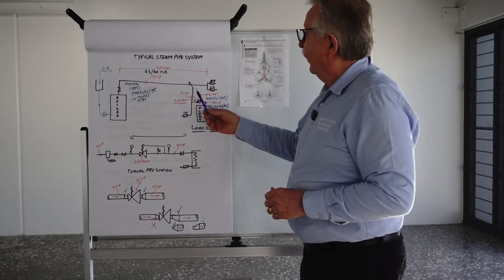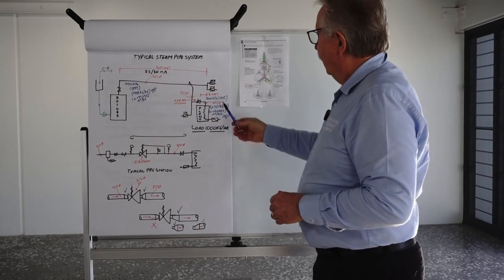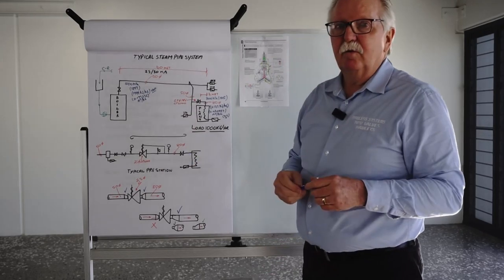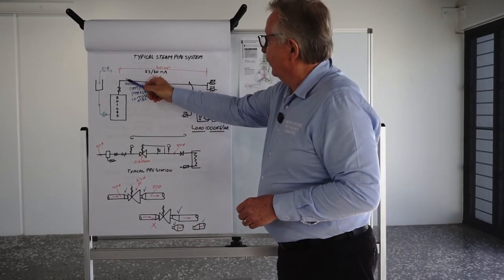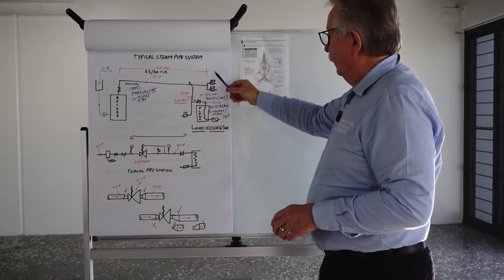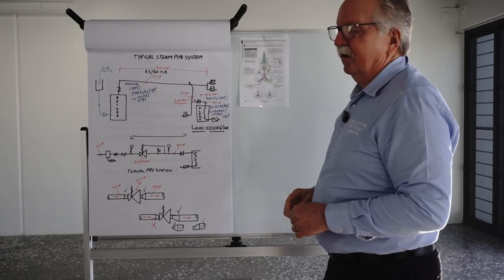So if you take this scenario where we've got 60 metres of pipe, if we were to put our pressure reducing valve here, which you could do if you wanted to, and we could reduce our 1000 kPa down to 300 kPa and deliver steam through the process to the plant at 300 kPa.